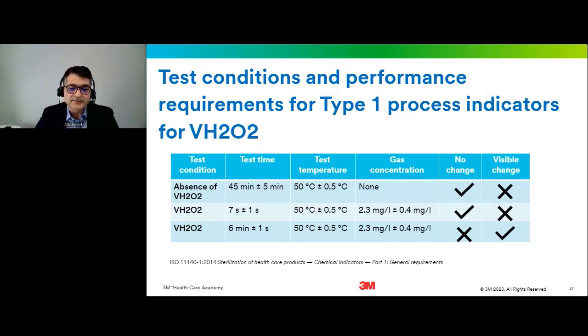As you can see in the second row, at 7 seconds there should be no visible change. But at 6 minutes plus 1 second at the specified time and temperature, with 50 degrees centigrade and 2.3 milligrams per liter concentration, within the range of variance they have, there should be a visible change. So within 6 minutes, a type 1 should have a visible change, which is a positive one. Now you can compare it to the cycles that you have, and it can give you an idea at which portion of the cycle you will get a good response from a type 1 indicator, because that's how they have been designed to be used.